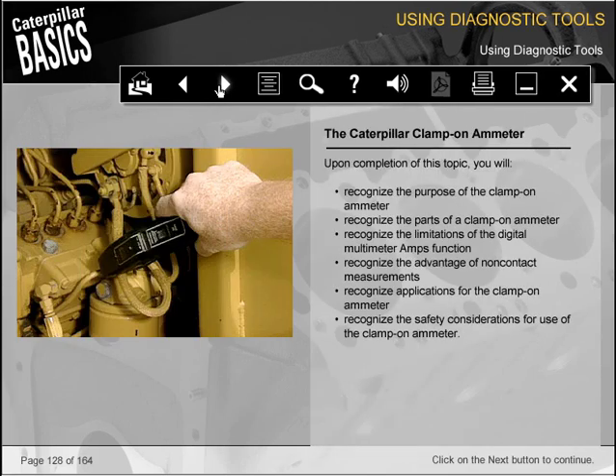Upon completion of this topic, you will recognize the purpose of the clamp-on ammeter. You will be able to recognize the parts of a clamp-on ammeter. You will recognize the limitations of the digital multimeter amps function. You will recognize the advantage of non-contact measurements. You will recognize applications for the clamp-on ammeter. You will recognize the safety considerations for use of the clamp-on ammeter.